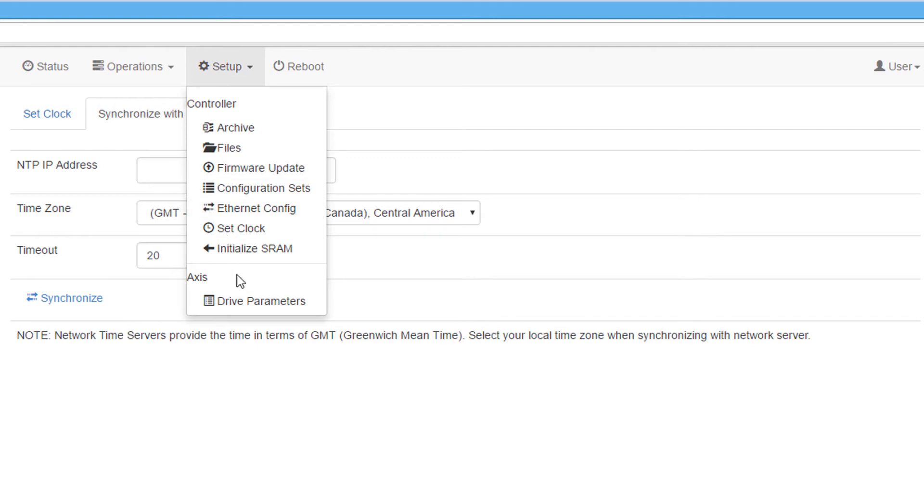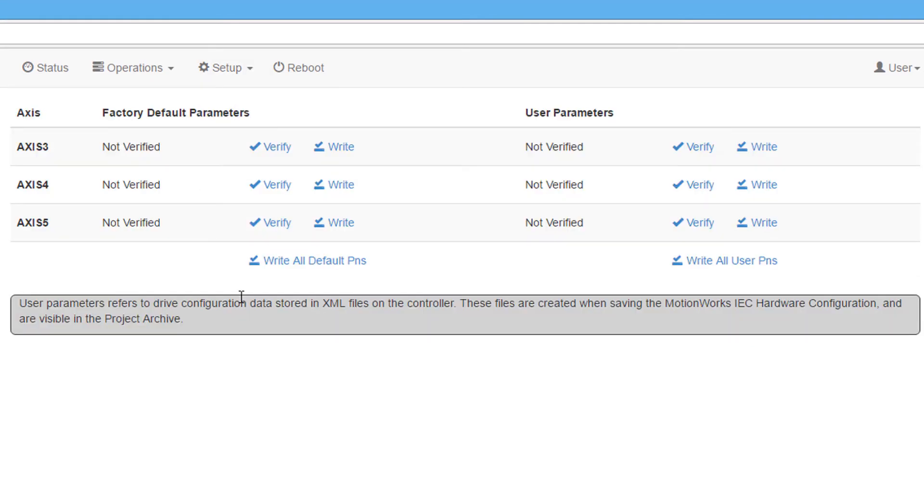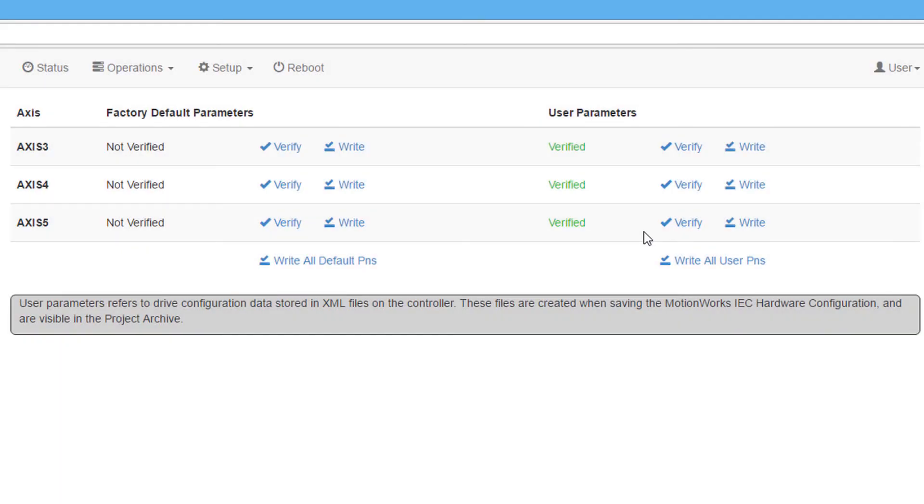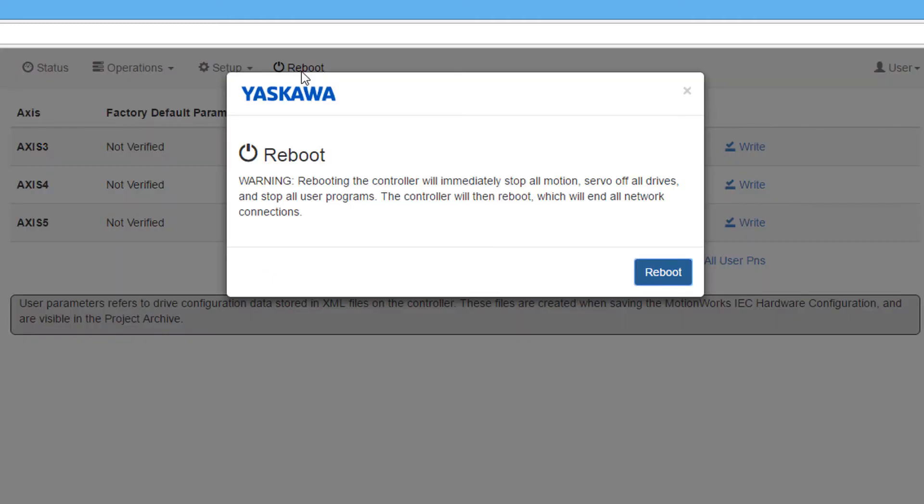The drive parameters function allows the default or user drive parameters stored in the controller to be written to the servo amplifiers. This function can be used when commissioning a new system from a project archive or when replacing servo amplifiers. The reboot function reboots the controller along with the control portions of the connected servo amplifiers.